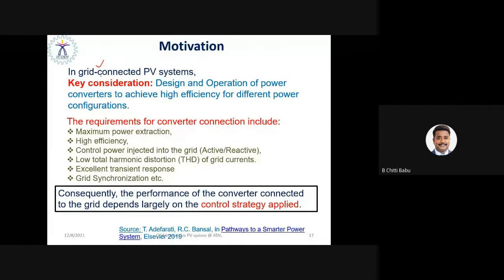So in a grid connected system, the main consideration is the design and operation of the power converter to achieve high efficiency for different power configurations. The overall conversion efficiency, the system efficiency, should be high enough. That is a very important thing. While integrating solar PV with the utility grid, the power producer has to meet certain requirements imposed by a power system operator or transmission system operator, called the TSO. The TSO imposes certain requirements on a power producer so that they can accept the power generated by a particular company, right? These requirements are called grid connection requirements or grid code compliances.